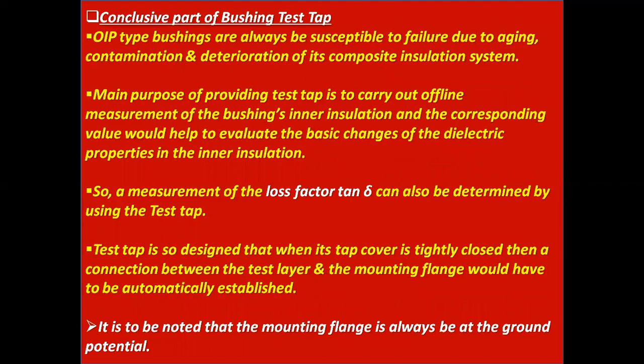Conclusive part of bushing test tap. OIP type bushings are always susceptible to failure due to aging, contamination, and deterioration of their composite insulation system.